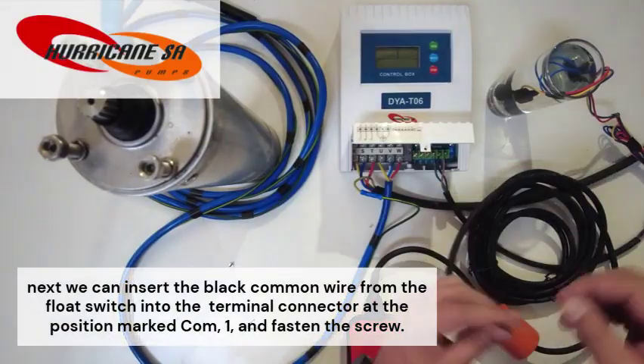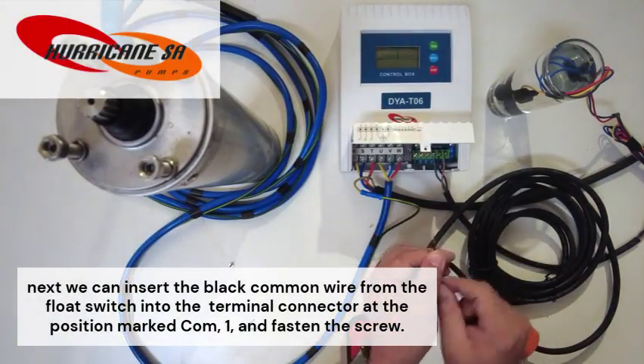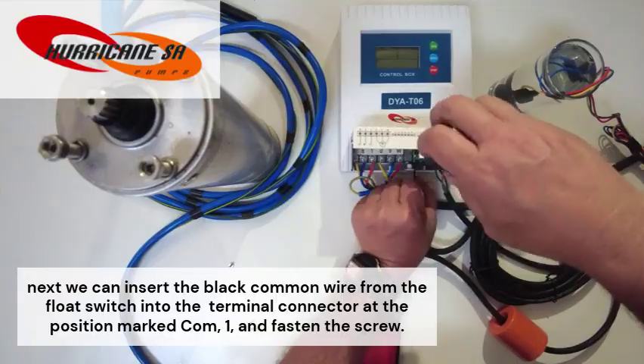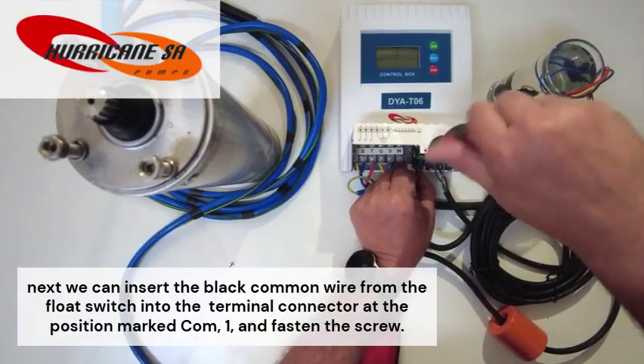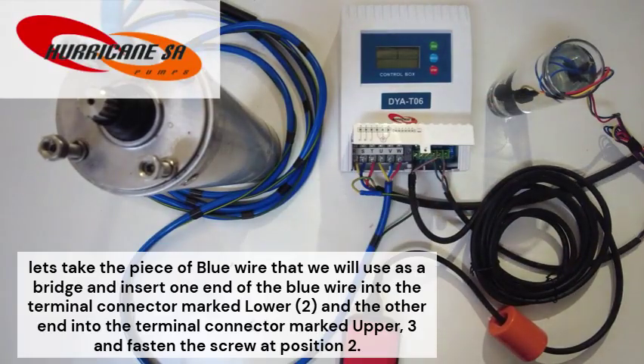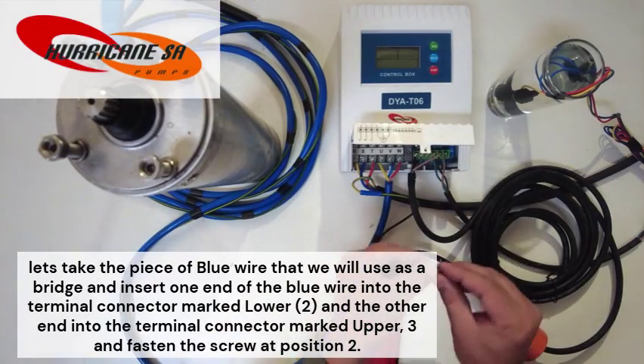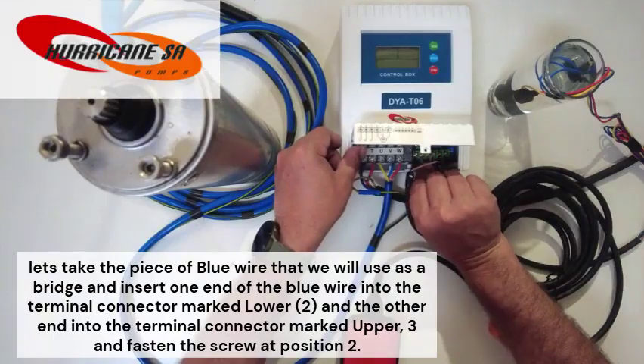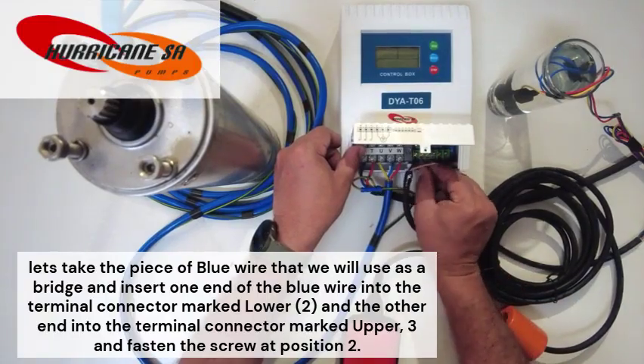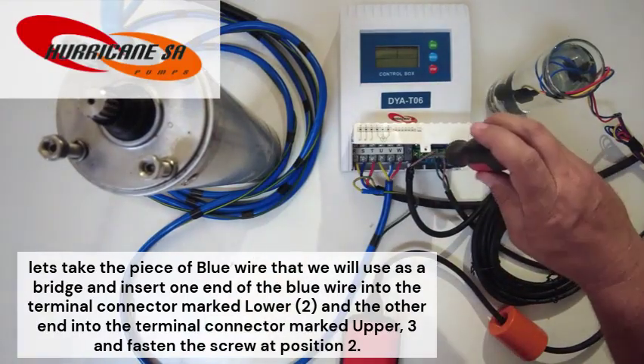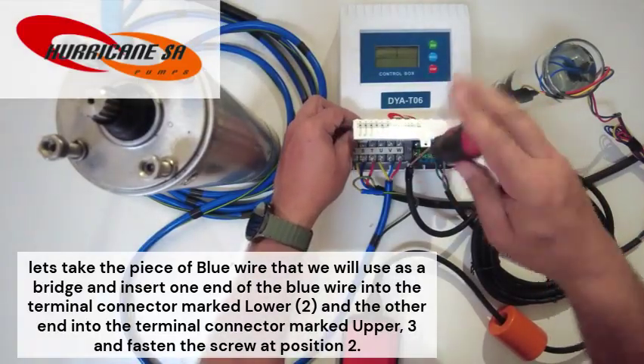Next, we can insert the black common wire from the float switch into the terminal connector at the position marked COM1 and fasten the screw. Let's take the piece of blue wire that we will use as a bridge and insert one end of the blue wire into the terminal connector marked lower 2 and the other end into the terminal connector marked upper 3 and fasten the screw at position 2.